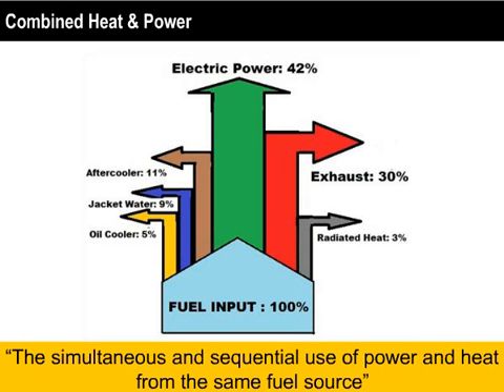That is a green arrow here in the center, and a lot of heat that is dispersed in the engine while it runs. This heat is here dispersed in different formats and different temperatures. And look at the exhaust, for instance. Exhaust is gas, and it's around 500 degrees C, about 900 degrees F. And how can we capture it? If you look at the other side of the arrow, you see also jacket water. Jacket water is water at 200 F, more or less, 90 degrees C. So the presentation today will be how can we capture and value on the top of the power the rest of the heat that is here at different formats.